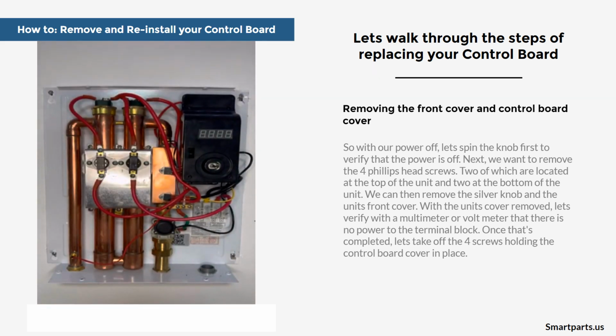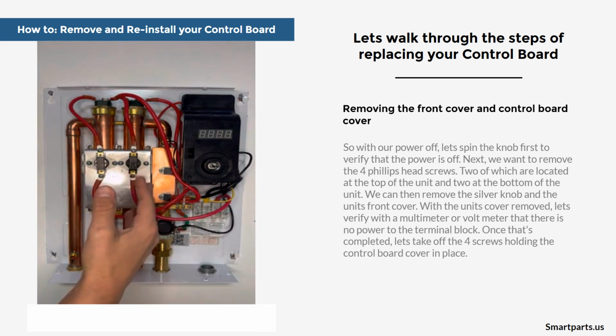And once you remove that front cover, the next step is to verify that we don't have power. Obviously this is a demo unit, but for you, you're going to want to use a multimeter or a voltmeter at each leg to verify that there's no incoming power to the unit.